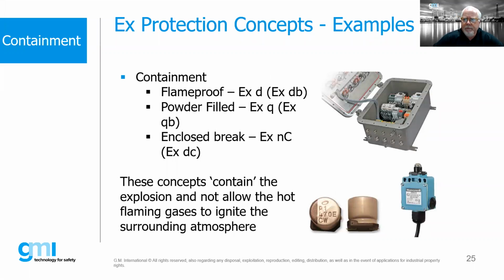Now, containment is what many people are familiar with, the flame-proof concept, where we basically assume we're going to have arcing and sparking components. Those gases and vapors are going to migrate at some point during normal atmospheric changes to the inside of an enclosure. When a contactor makes or breaks, we potentially could have an arc. If we have that proper mixture of fuel gas on the inside of that enclosure, we'll have a contained explosion. So that explosion shall be contained inside that enclosure, and all of the hot flaming gases must be vented, and they must be cooled to make sure that they don't ignite the gas surrounding the enclosure. So those are typically done with flame paths or joints.